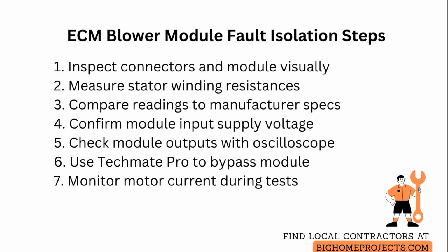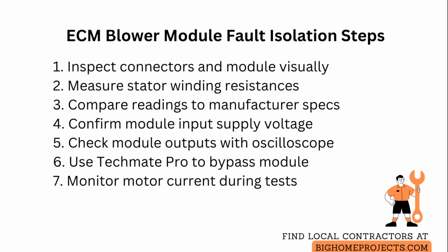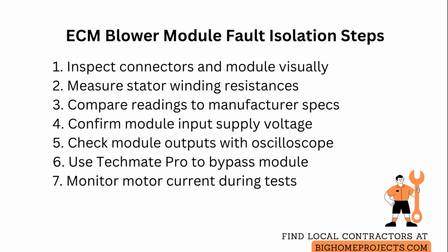With power restored and safety precautions in place, confirm that the module receives the correct incoming direct current supply and any required control voltages from the system control board by measuring for steady supply voltage at the module input while the system is calling for blower operation.